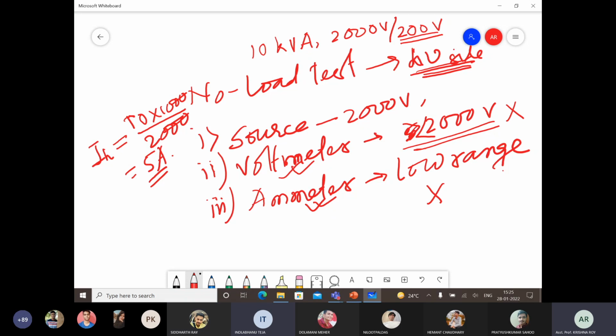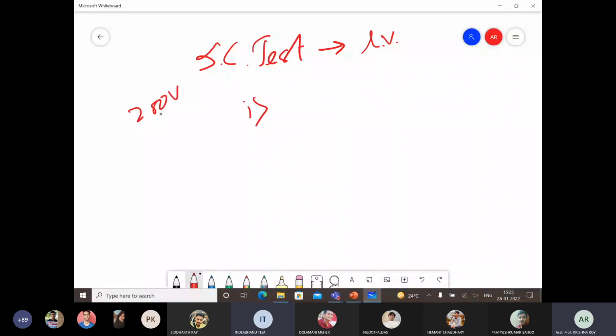Yes, sir. Okay. So next is short circuit test, SC test. If we want to perform it on the low voltage side, normally it is performed on the high voltage side. So if we want to perform it on the low voltage side, then what are the requirements? Again, see, first of all, we have to give a very small voltage to circulate rated current. Okay, so source for the same transformer, suppose, so 200 volt, it's 2 to 12%. Source is required. Okay, so that is easily available.